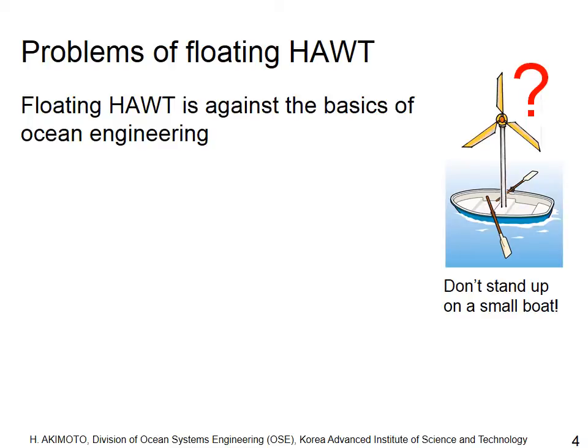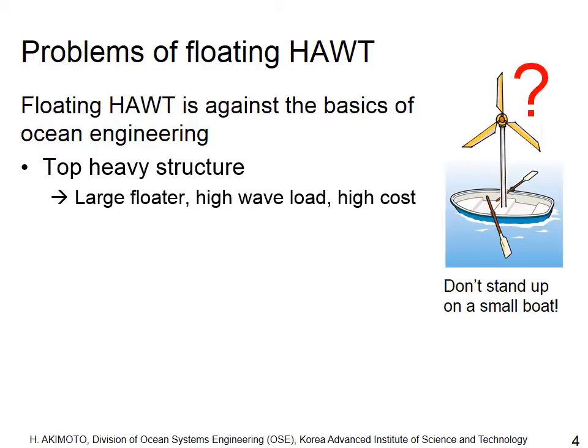At present, the mainstream concept of floating offshore wind turbines is the horizontal axis wind turbine, mainly because they have been quite successful in onshore applications. However, the floating horizontal axis wind turbine is against the basics of ocean engineering and naval architecture — it is a top-heavy structure. The main electromechanics are on top of a high tower, and to keep its upright position offshore, we need a large floater system.